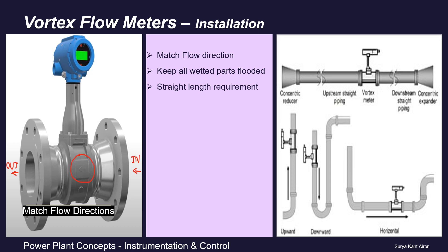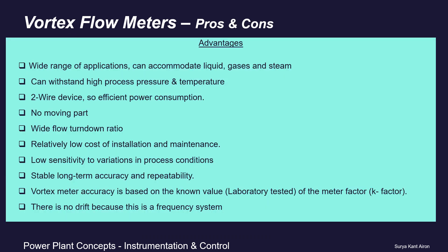As a rule of thumb, if the recommended minimum straight length is 10D upstream and 5D downstream, it is desirable to double these lengths for better accuracy — that is 20D upstream and 10D downstream.